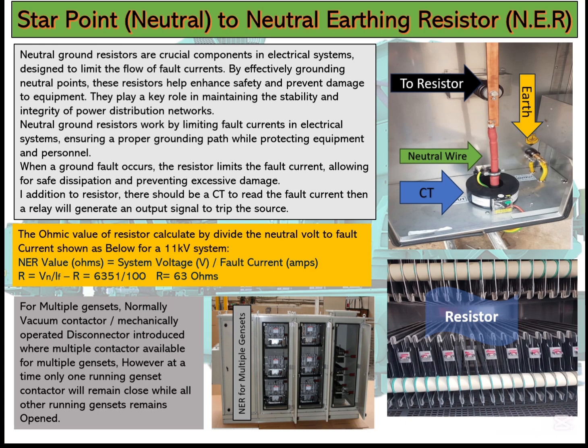So when any short circuit current passes through the neutral, the CT will detect it and signal your relay. If the relay meets the threshold and the set points, it will trigger the engine to stop. So this is the safety of your source. Normally, this NER is used with alternators and transformers in substations. This is our power connections, load connections.